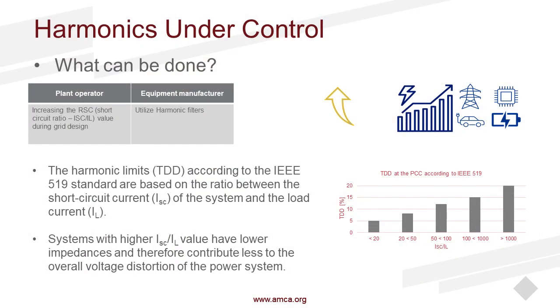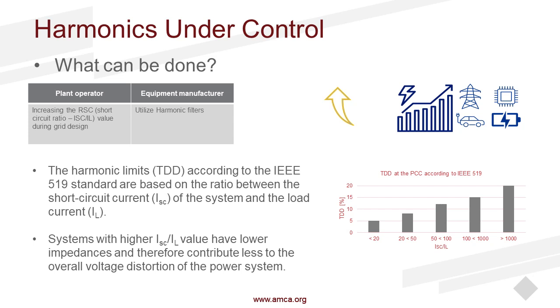On the design side of your grid, we can look at the ratio of our short circuit current and our load current, which is where IEEE 519 comes into play. What it's saying is, the bigger the ratio you have, the less impedance you have, so the less stress you have on your grid. Here in this graph, we can see that a higher ratio means we can have a higher total demand distortion. So this is your total grid. It's not necessarily looking at one component of the grid, it's looking at the total grid. So in the design stage, you can then look at, okay, I need more TDD, I need a greater ratio.